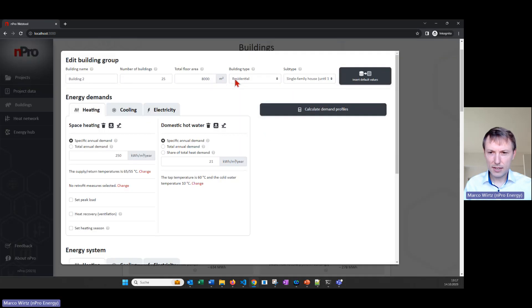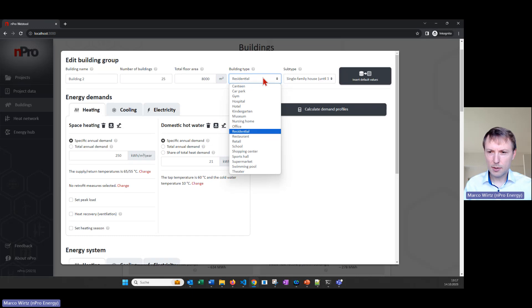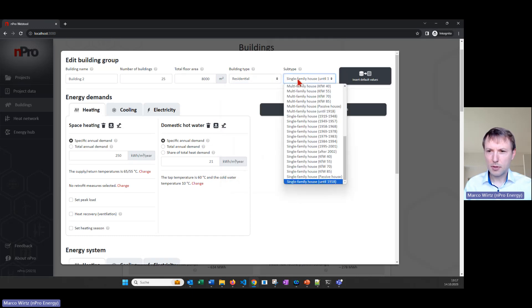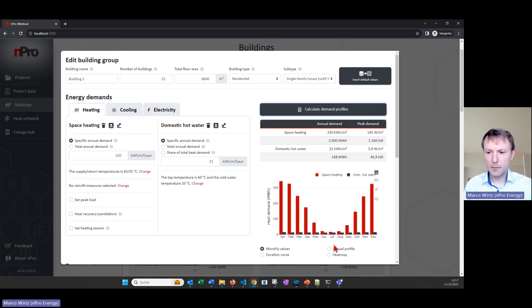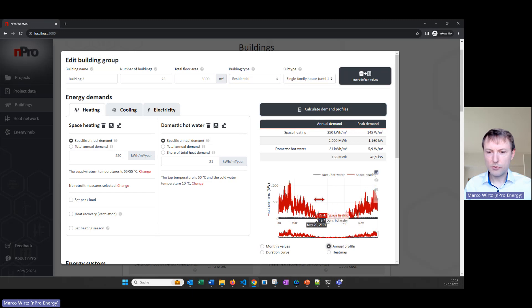In the building settings we can define the building type, subtype, and the demands. We have space heating demands and domestic hot water demands, and we can provide a value in kilowatt hours per square meter. Then we click on 'Calculate Demand Profiles', which always generates hourly resolution profiles. One important parameter is the supply and return temperature.